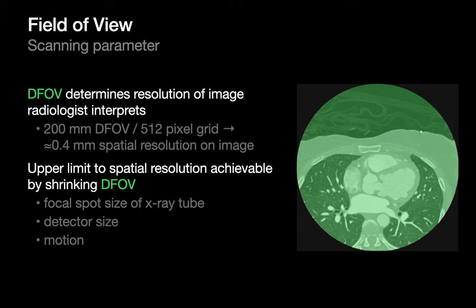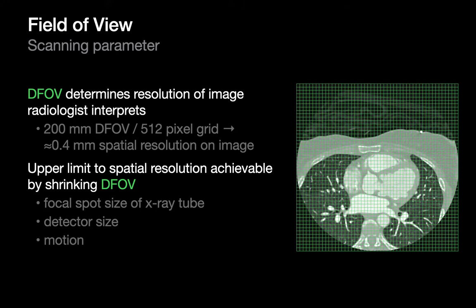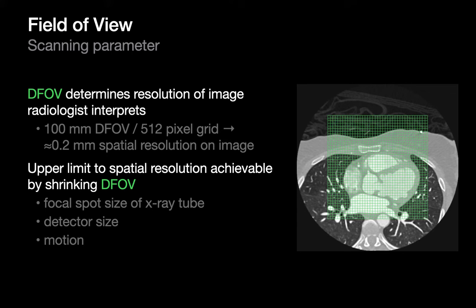You can do a rough calculation of DFOV's effect on spatial resolution. If our CT image is a 512×512 pixel grid and the DFOV is 200 mm, then 200 mm ÷ 512 pixels means every pixel represents 0.4 mm. If the DFOV is 100 mm, then 100 mm ÷ 512 pixels means every pixel represents 0.2 mm instead — twice the spatial resolution.